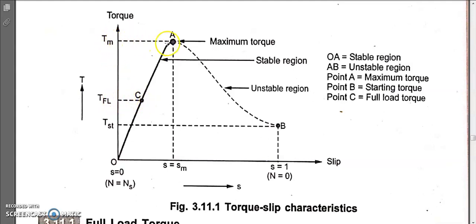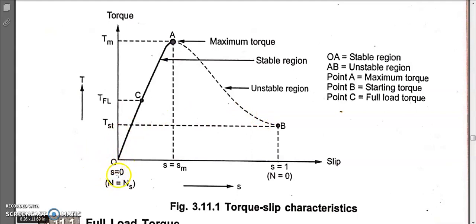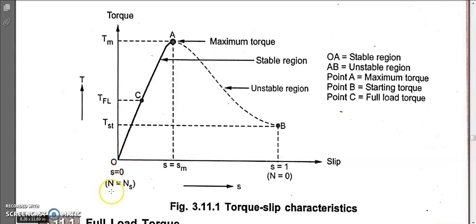Full load torque TFL is always less than the maximum torque. Always operate the motor from O to A, not from A to B. Near slip equals zero, rotor speed is almost equal to synchronous speed ns. During light load or no load conditions, rotor speed is almost equal to stator synchronous speed.